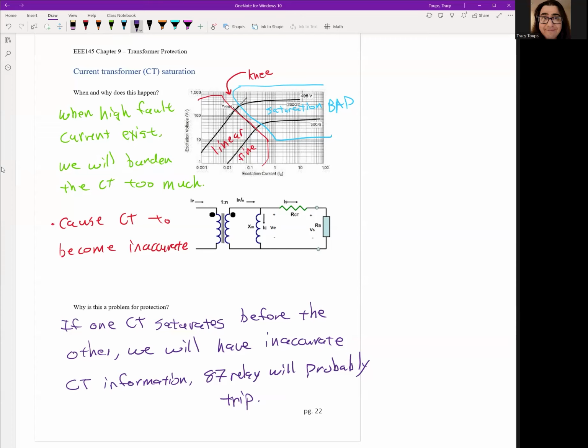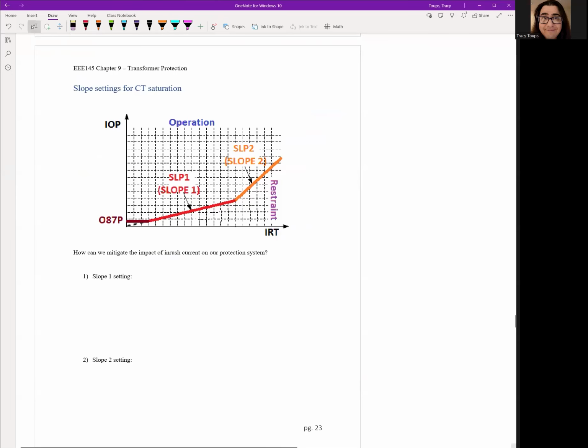Okay, so imagine you have a transformer, the high voltage side CT works fine, but then the low side CT enters saturation too quickly, and then we lose information there. Now it's a one-sided current, and now the 87 relay just flips out and trips offline. Okay. This is an issue, especially for external faults where the current rides through our transformer to the next section. We don't want our transformer to trip for an outside fault.